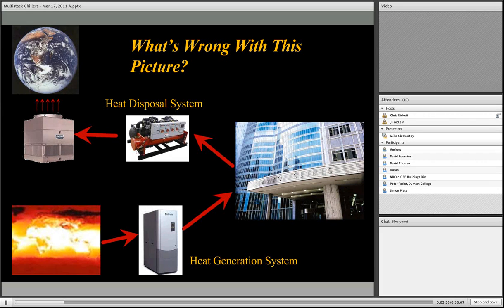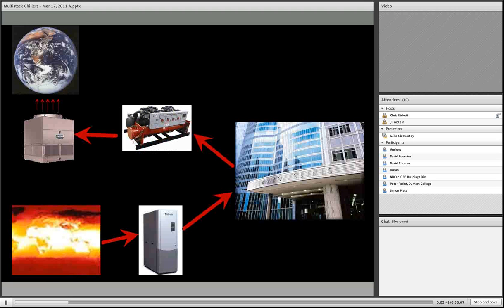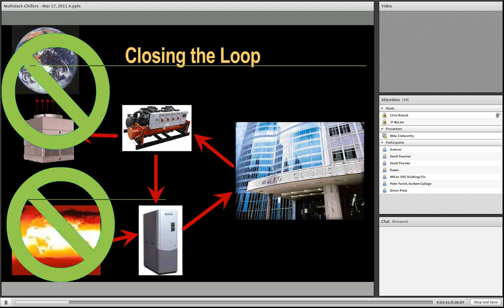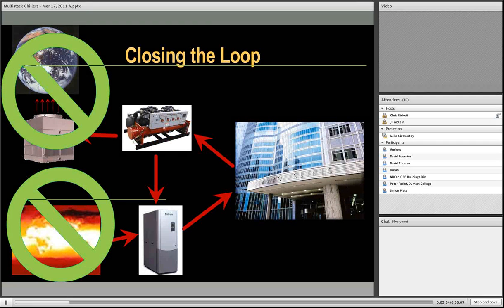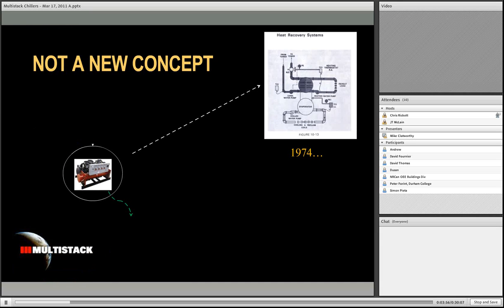Here, this diagram really shows a heat disposal system and a heat generation system. The heat disposal system is the chiller. The heat generation system is the boiler. And we're using electricity in the case of the chiller to move heat out of the building. But if we need heat, we're using a boiler and we're burning natural gas or some other substance, possibly fuel oil, to create heat. Not necessarily a good thing. And so how do we close that loop? How do we stop doing that?